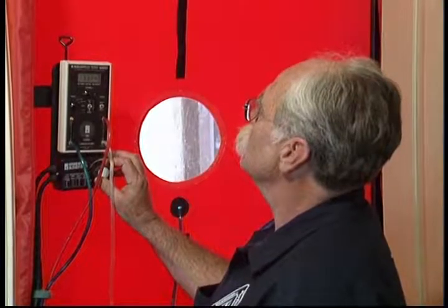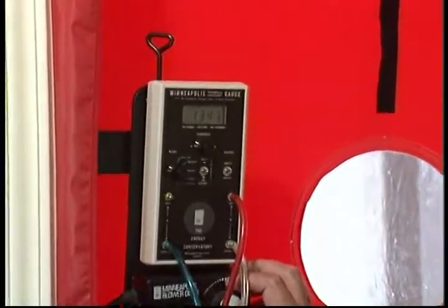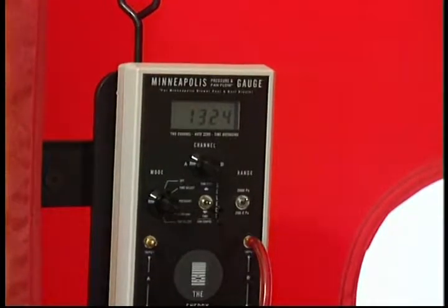Yes, sir. And what are the typical ranges in leakage that you find on California homes? Oh, I've got them as low as 400 and up to 9,000 cubic feet per minute, Steve. Really? Well, yeah, wide range. Now, what's typical for a 2,000 square foot house? Oh, around 1,500 to 2,500 cubic feet per minute.